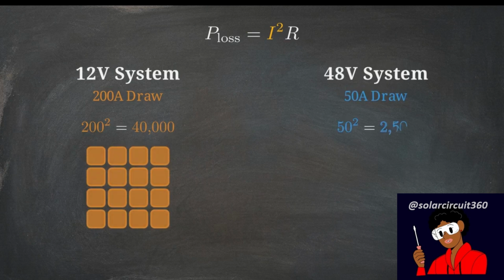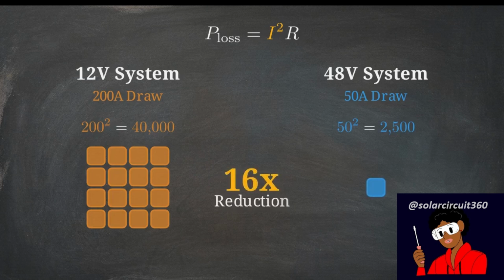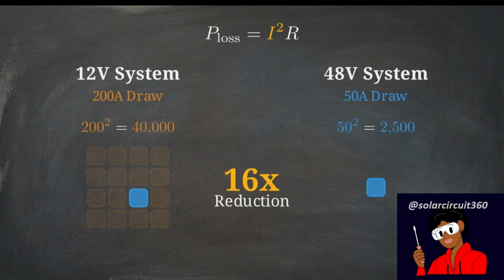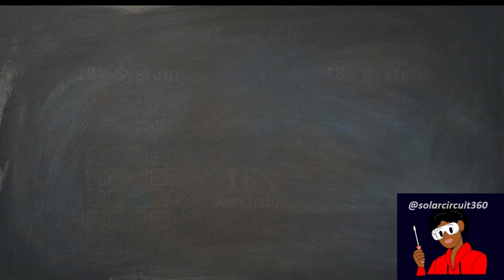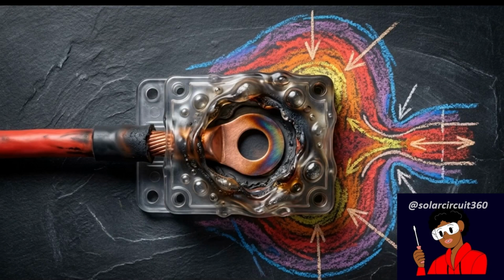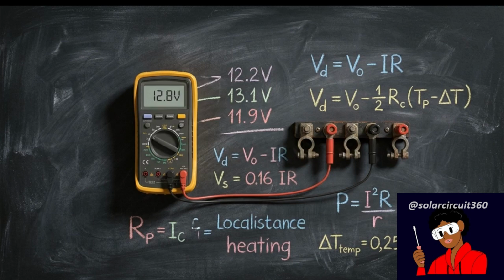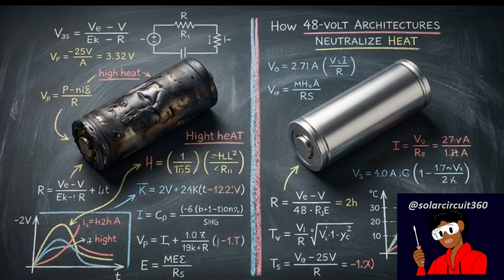Squaring the 12-volt system's 200 amp draw yields a heat multiplier of 40,000. The 48-volt system's 50 amp draw yields only 2,500. Quadrupling the voltage systematically drops thermal waste by a factor of 16. In 12-volt systems, that immense heat concentrates at physical choke points, baking battery terminals, cable lugs, and fuse blocks hour after hour. Over time, this localized resistance heating creates slight voltage variations between cells, drifting large parallel strings permanently out of sync. Because heat drives the chemical degradation of energy storage, 48-volt architectures mathematically neutralize the primary source of early hardware failure.